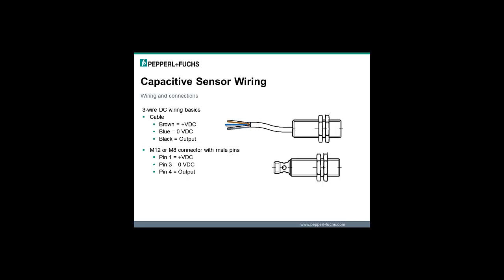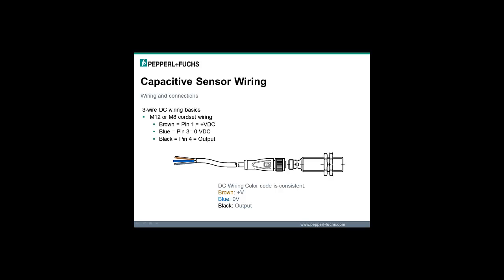For sensors with integral M12 or M8 connectors, the 3-wire DC capacitive sensor wiring is defined as pin number 1 plus voltage connection, pin number 3 power supply common or zero volt connection, pin number 4 output connection. Conveniently, the wiring color code extends to the external cable connections when using a cord set with a sensor that has an integral connector. Here you can see that when using a 3-wire or 4-wire cord set, the wiring colors that you connect to use the sensor are the same: brown, blue and black.